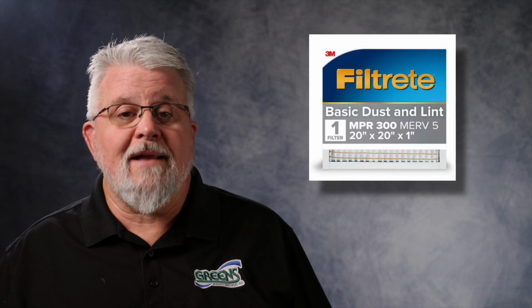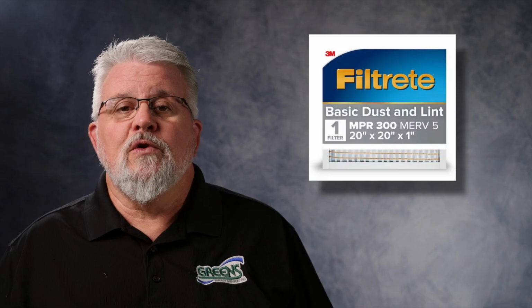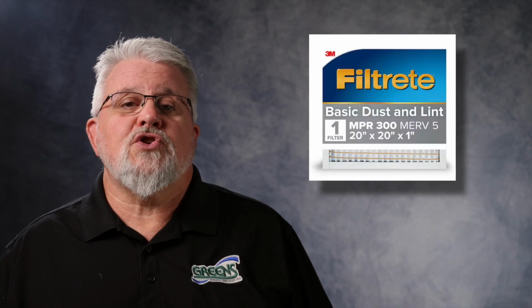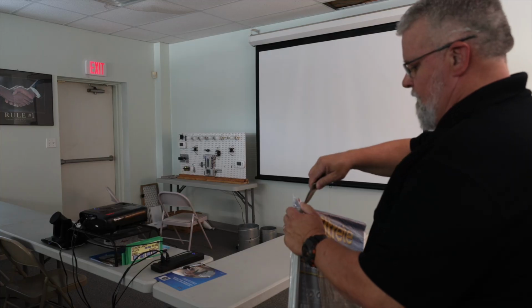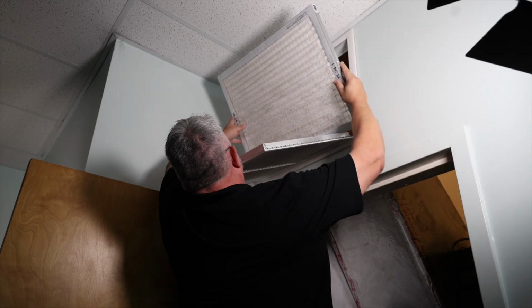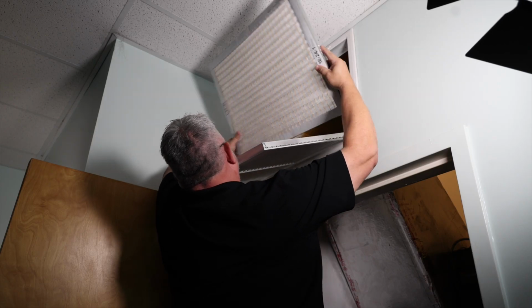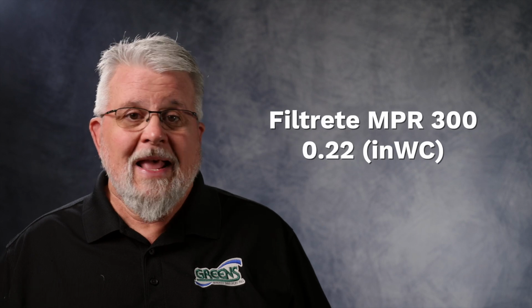This is a MERV 5 filter, and it uses electrostatically charged polypropylene media. Basically, the filter material is designed to attract airborne particles. This filter came in at around $6, but structurally, I found it still somewhat flimsy. Now, here's where things started to get interesting.